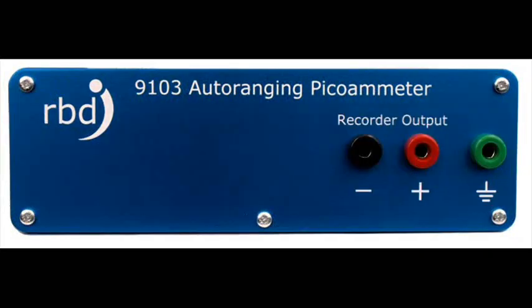The BNC has 550 volts of isolation with respect to ground. On the back of the 9103, there's recorder output jacks, which are plus and minus 2 volts DC per range, and there's also a chassis ground connector if you want additional grounding for the chassis.